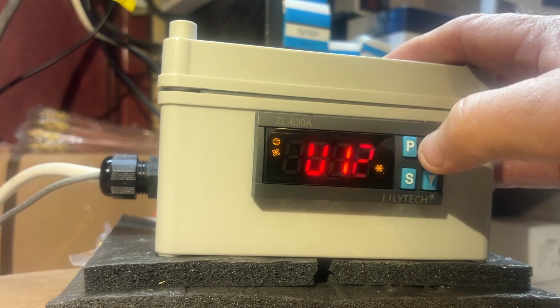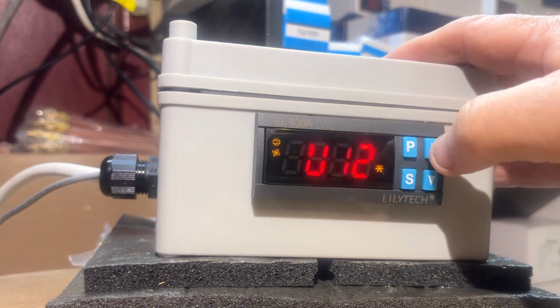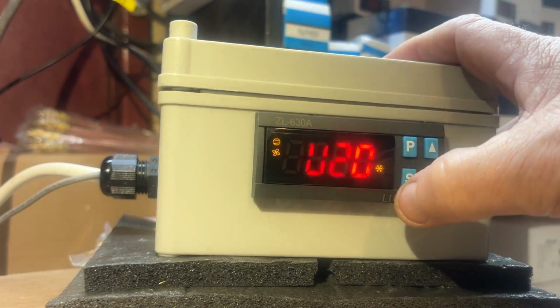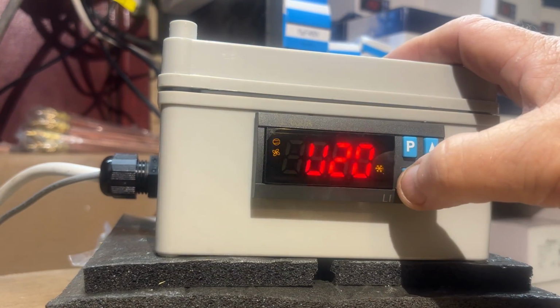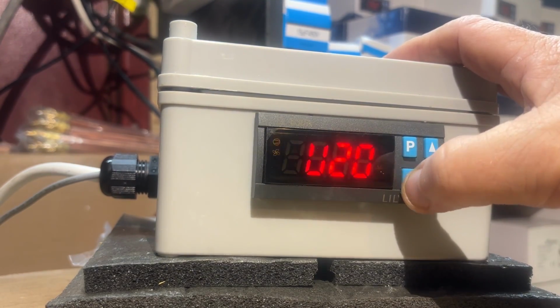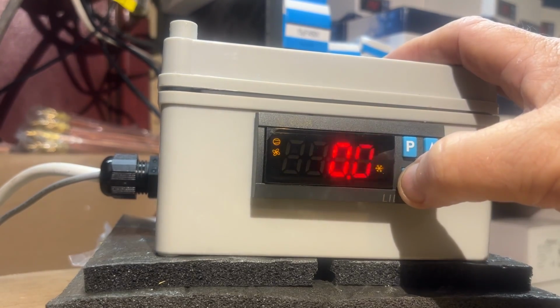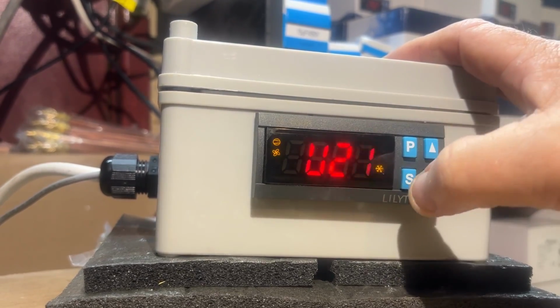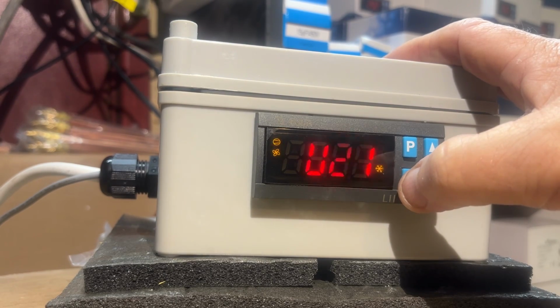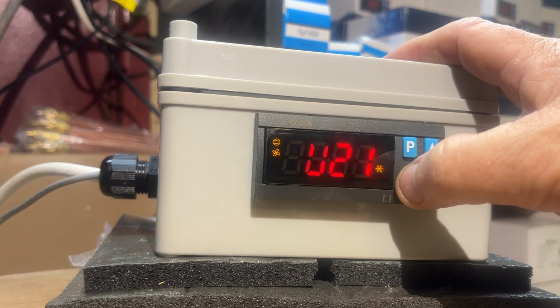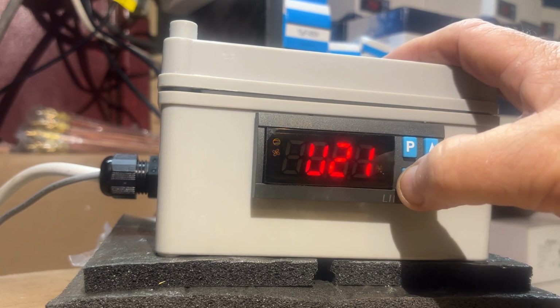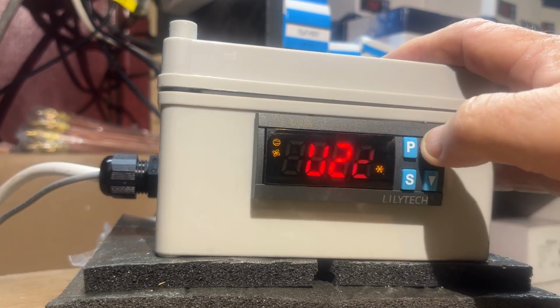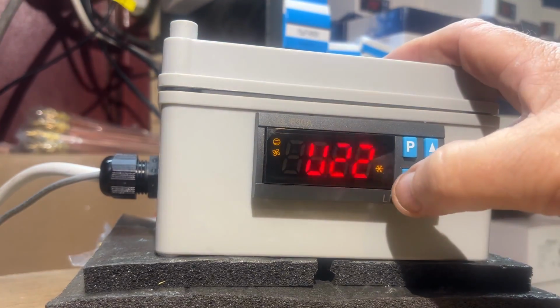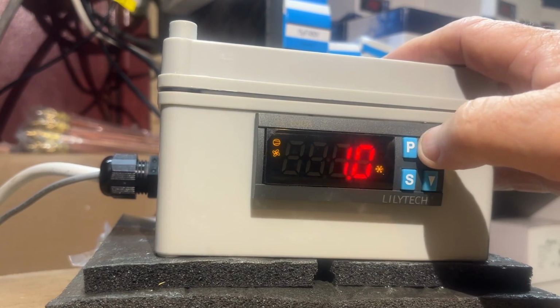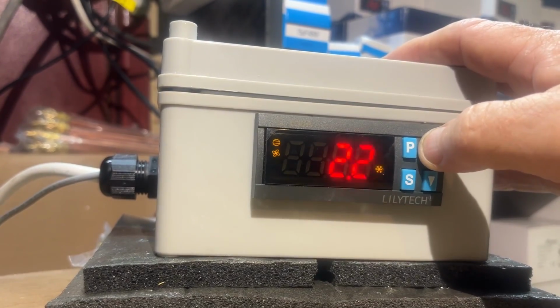Okay, so 12, I don't think we need to worry about. We need to get to 20. Now 20 is the ambient temperature, or the room temperature calibration. That's on 0. If you have to calibrate it, there it is. 21, that's the defrost sensor calibration. I've got all this at the end as well on a photo. So that's on 0. So 22 is a differential. Let's set that to 3. So it's going to go between 2 and 5.